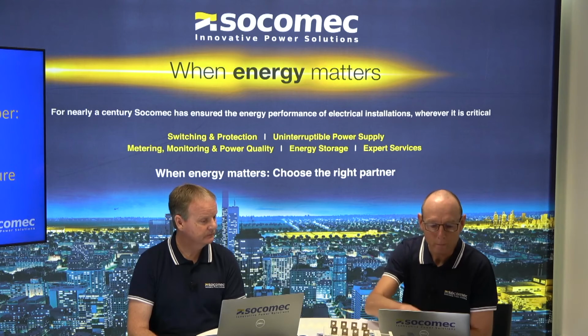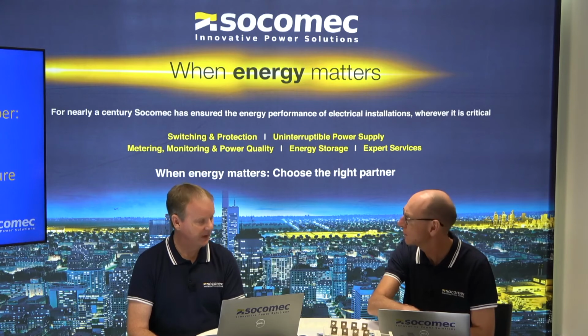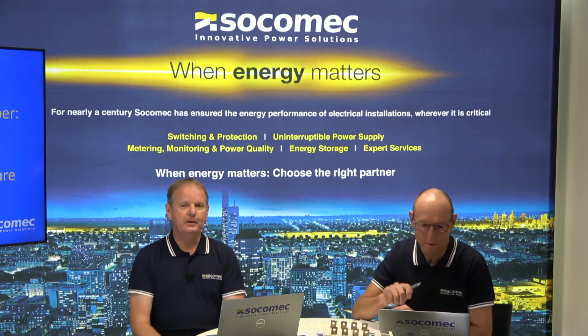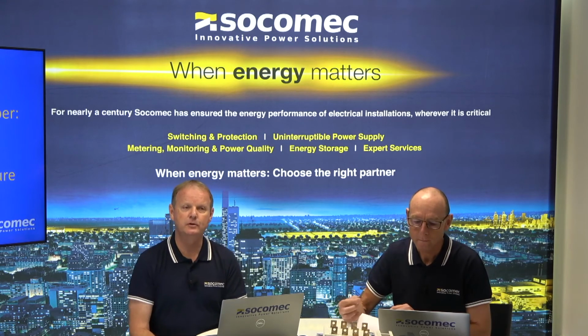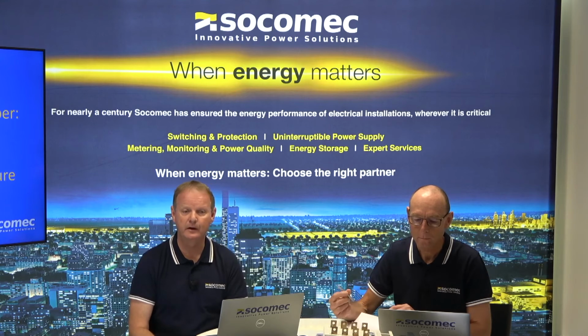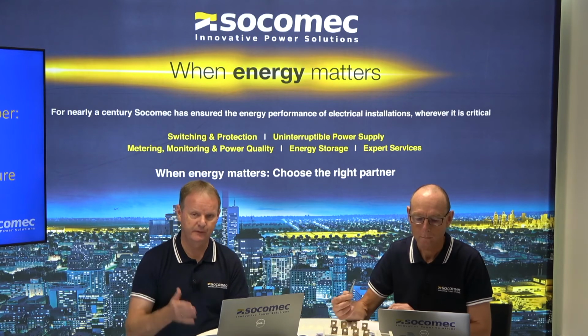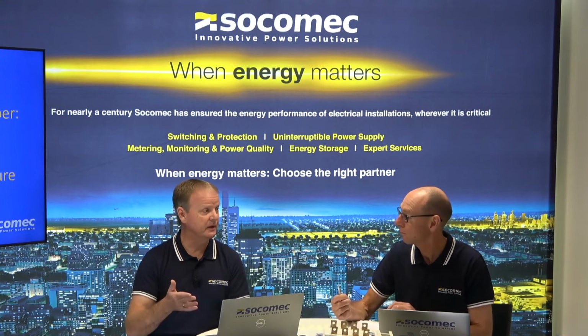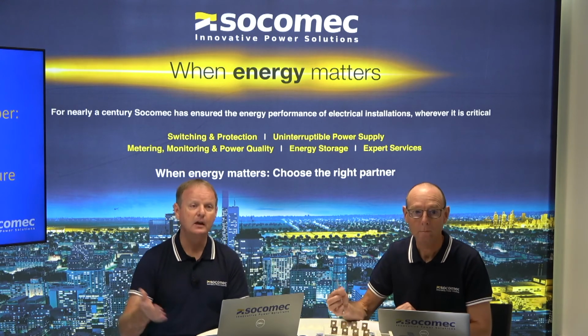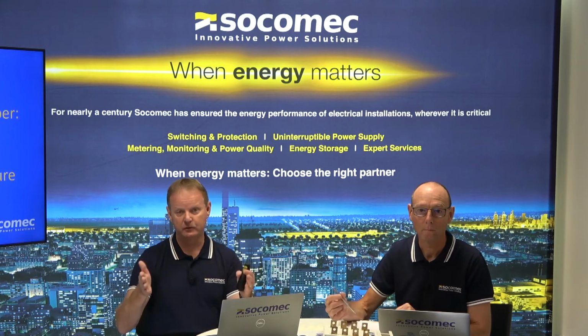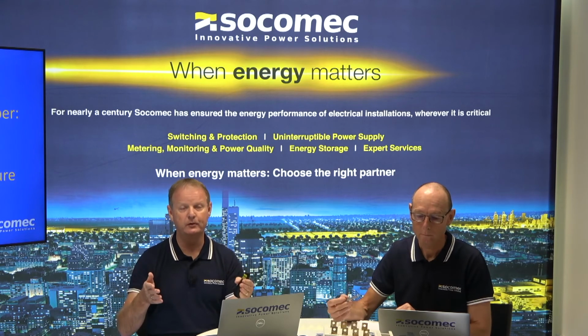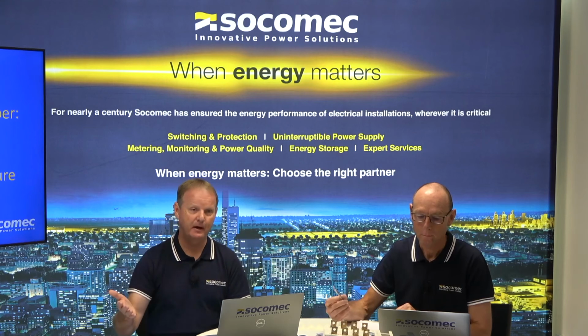8519 calls for single or dual line bypass. Yes. Could you just re-explain? Okay, so you can use single or dual. Really what the dual does against the single is give you an extra level of redundancy, an extra backup. So in a single, which is required under 8519, if you are on the first source, which can be the transformer, and you lose that source under a single line, you can't transfer. However, if it's on a dual line and you have 2 sources, generator and transformer, if you lose the transformer, while you do go into bypass mode, you can actually transfer the power over to the generator.